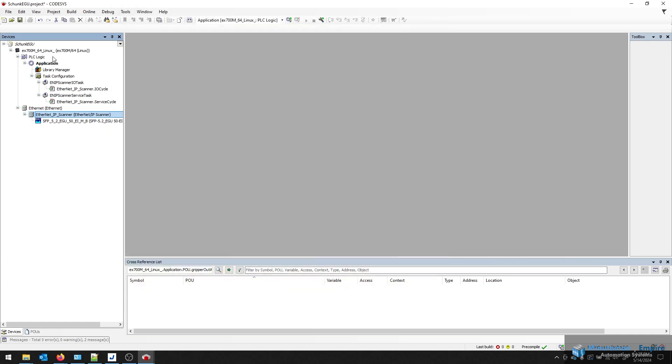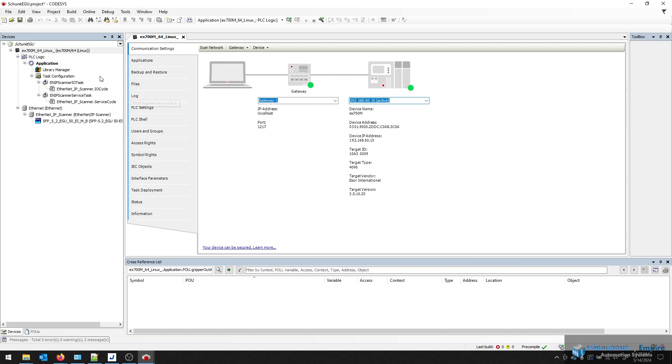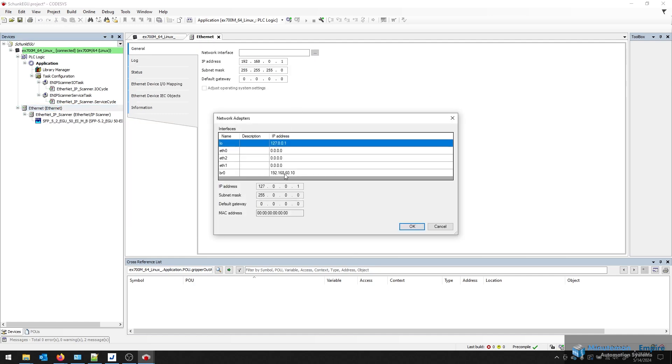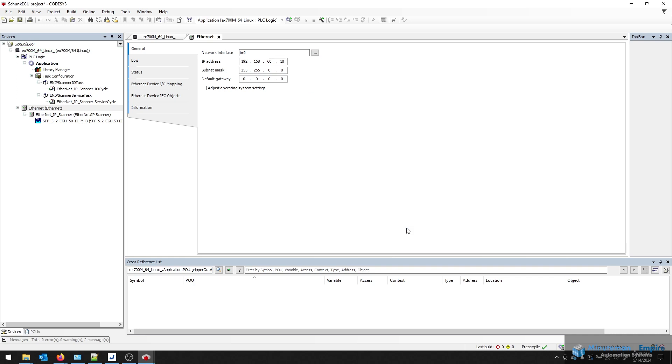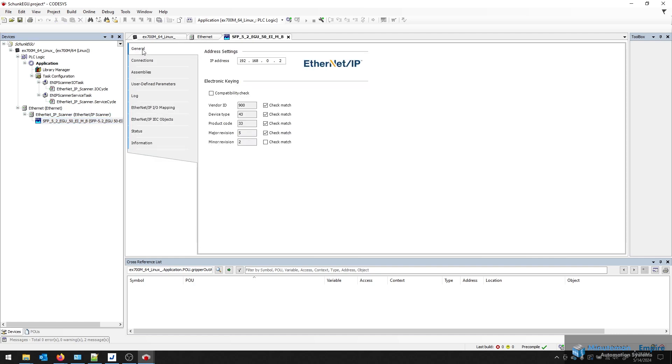A couple other configuration needs would be to set my IP address of my PLC in this case, and then go down to my Ethernet card and tell it to use the bridge device, which is allowing me to be connected to the Schunk gripper and my PLC at the same time. And under General, here's where we're going to type in the IP address of our gripper, which would be 60.11, as I demonstrated earlier.